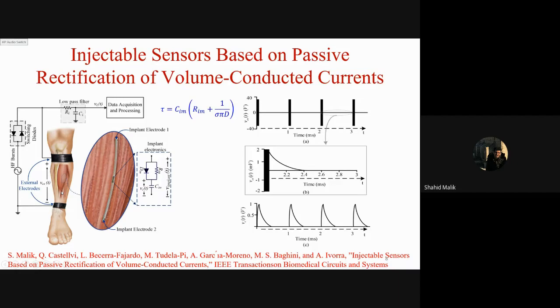So what we'll do, the same principle, we'll charge the capacitor, and once the burst ends, the capacitor will discharge through the conductivity of the tissue where we have implanted the implant. By measuring the discharging time constant, we'll be able to measure how much is the conductivity around the implant. This is the formula that will help us determine the conductivity, denoted by sigma. By measuring this tau, we'll simply get the value of the conductivity around the implant. This D is the implant electrode which we have fabricated.